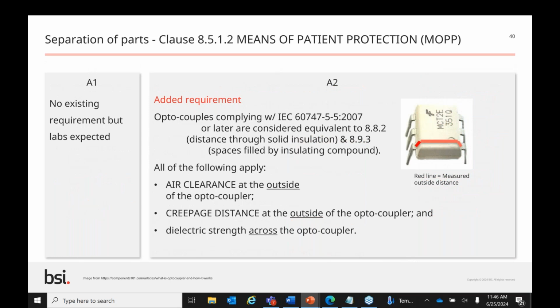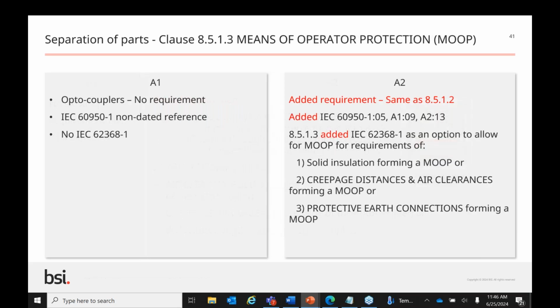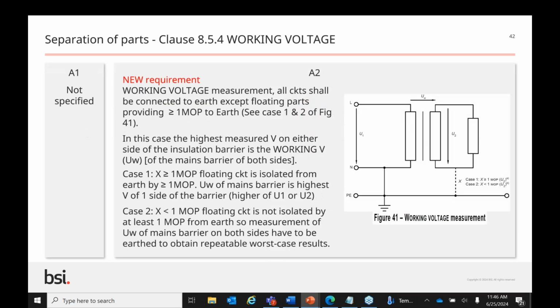So for this requirement for A1, most test labs were already testing to the requirement that didn't exist, but it's written in A2 now. So you have your spacing requirements in the top two bullets, and you have your dielectric requirement in the bottom bullet. Next slide, please. This is a cleanup clause just for your reference. Next slide. This requirement was added to define what is a floating circuit. Next slide.